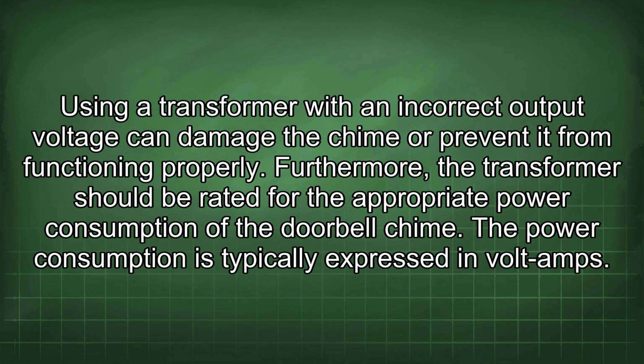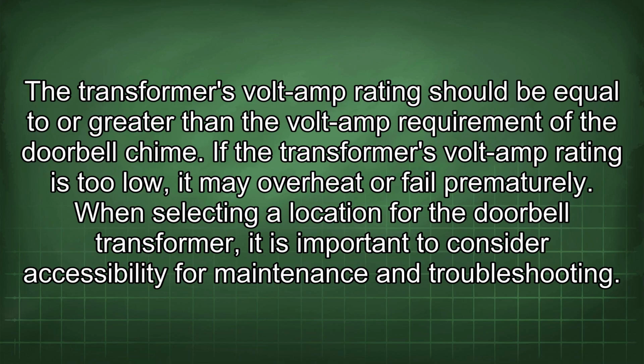Using a transformer with an incorrect output voltage can damage the chime or prevent it from functioning properly. Furthermore, the transformer should be rated for the appropriate power consumption of the doorbell chime. The power consumption is typically expressed in volt amps. The transformer's volt amp rating should be equal to or greater than the volt amp requirement of the doorbell chime. If the transformer's volt amp rating is too low, it may overheat or fail prematurely.